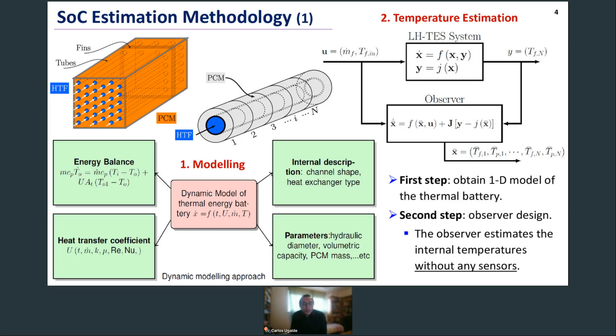The final step in the state of charge estimation methodology is the calculation, which requires first obtaining a specific heat against temperature curve of the PCM. This may be directly provided by a manufacturer. If this curve is integrated in time against a defined range of temperatures, the latent heat value is obtained, which is nothing else than the area below a curve. This latent heat value is used to calculate the state of charge, as it represents the energy per unit of mass that produces the phase change.